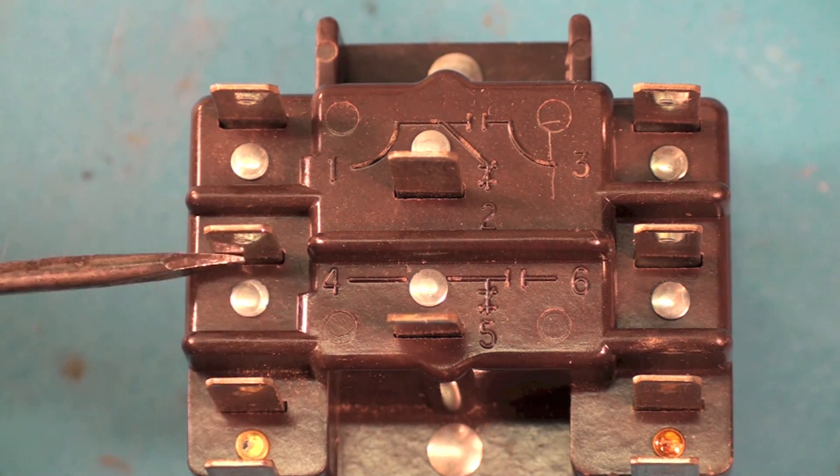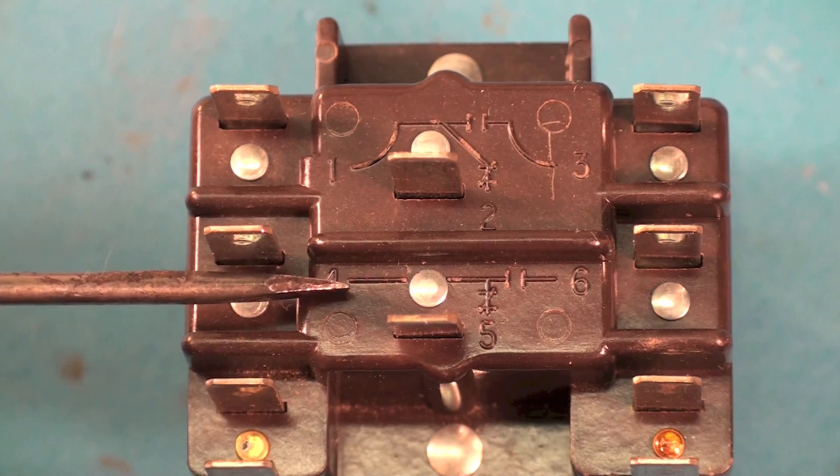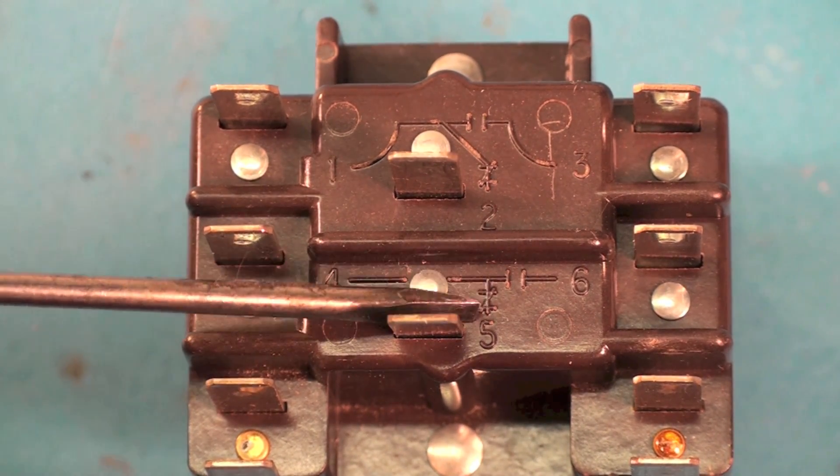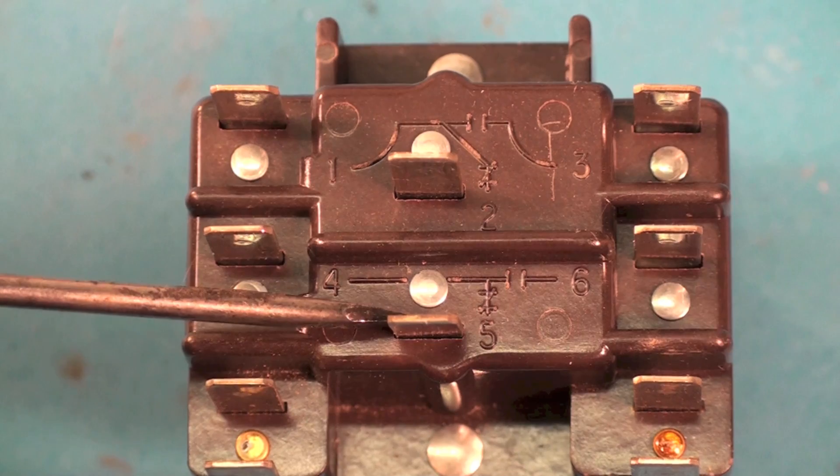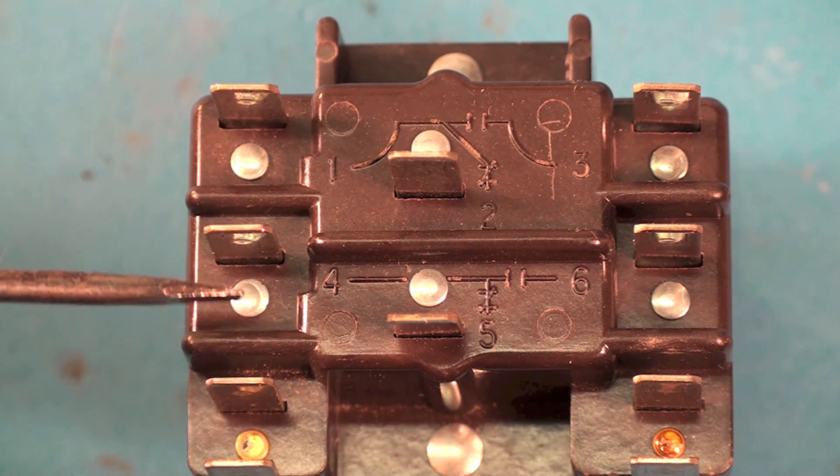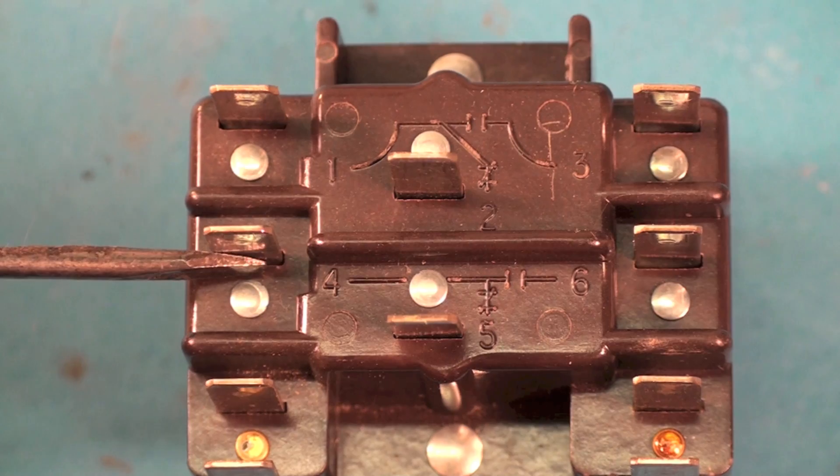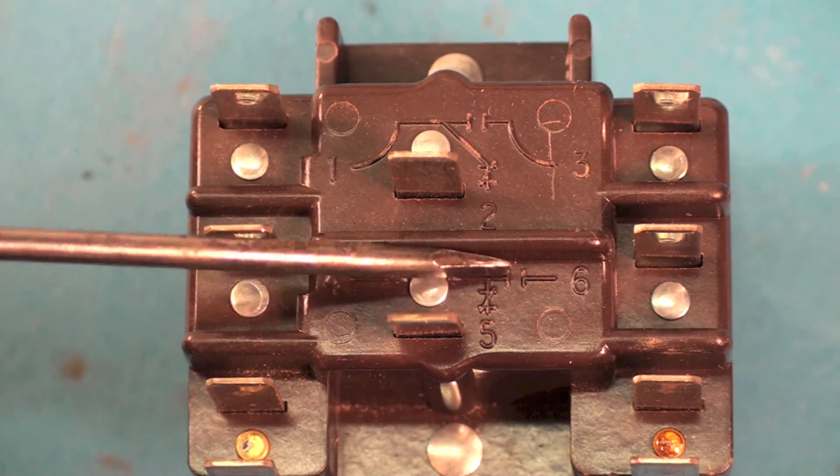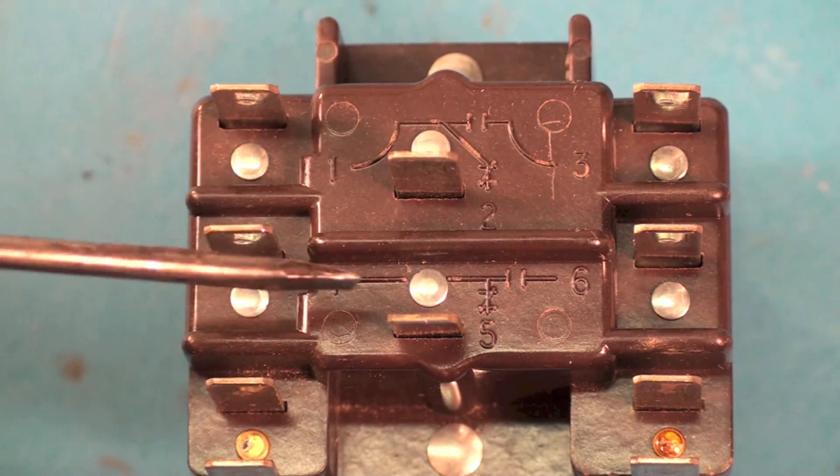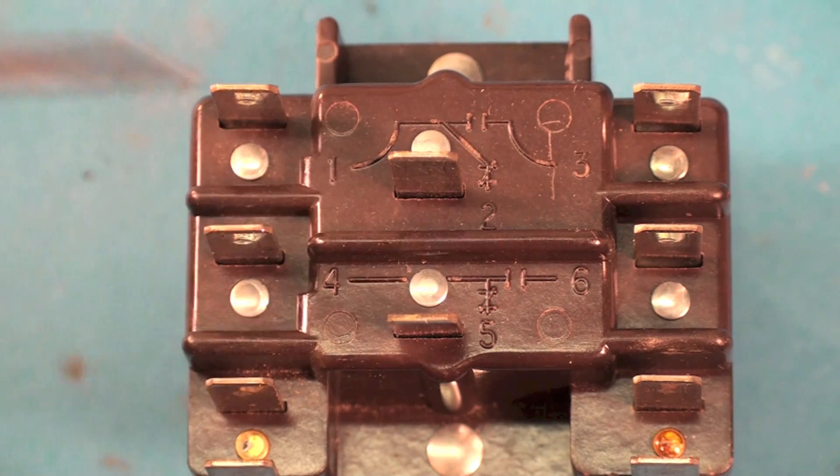Okay. So number four is the pole, because we've got this little wire going along here, comes to a normally closed contact, which is on five. So when this is de-energized, we have continuity between here and here, but we do not have continuity to number six, to this one. Energized, just switches. This one's open, this one's closed.